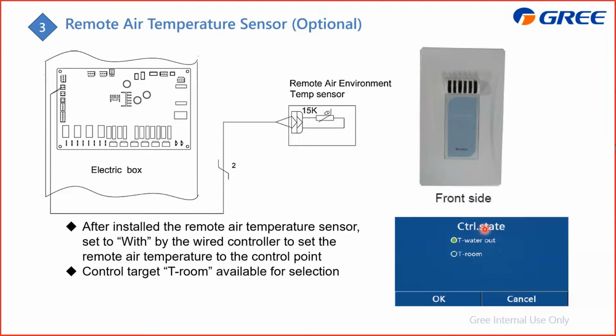And next is the remote air temperature sensor, and this is optional. That means you need to install a remote room temperature sensor to detect the room temperature instead of the water temperature to control the room temperature, which is to improve the accuracy. And also you need to select on the control state, where the target changes from the water out temperature to this room temperature.